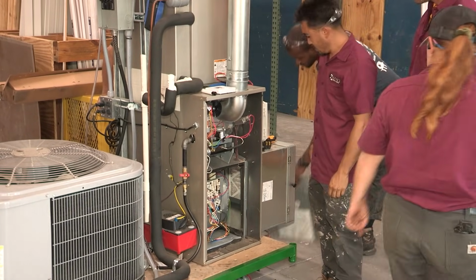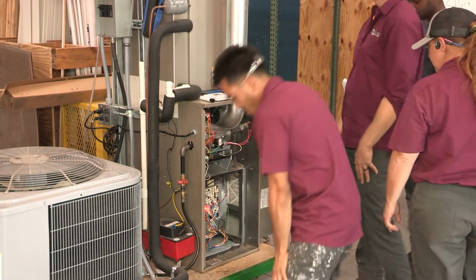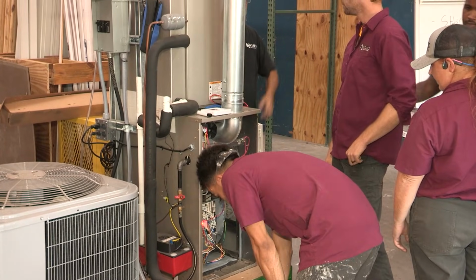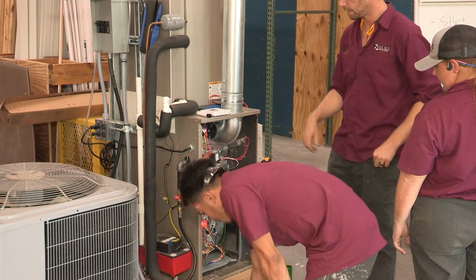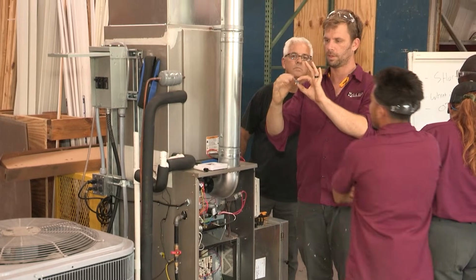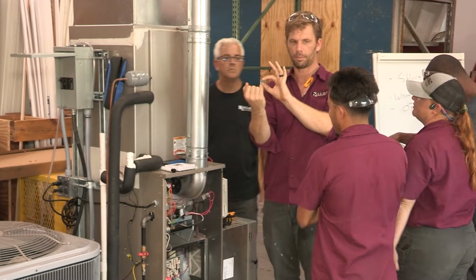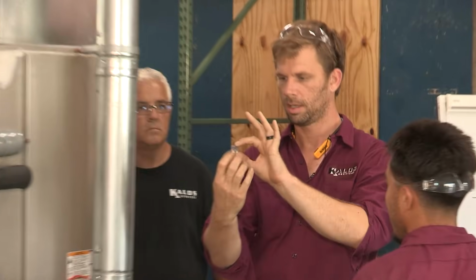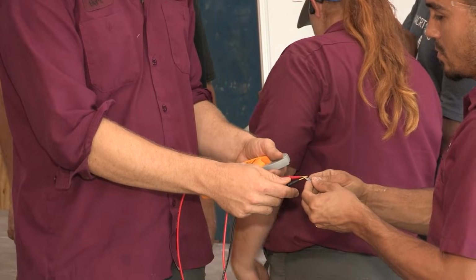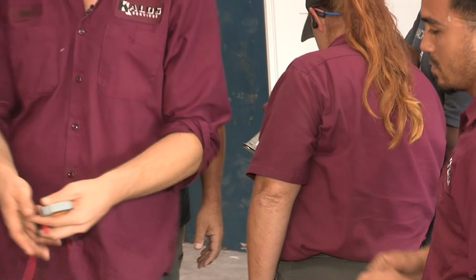Oh, panel's over there. We could either ohm it out or look at the top. So we could either ohm it out or look at it visually. If you look in through this fuse, you'll be able to see we have a black mark where it's actually burnt, and you can tell it's popped. But let's go ahead and test that with my meter. We're going to find out if we have a path. Still reading infinite, we don't have any path. So we've blown a fuse.